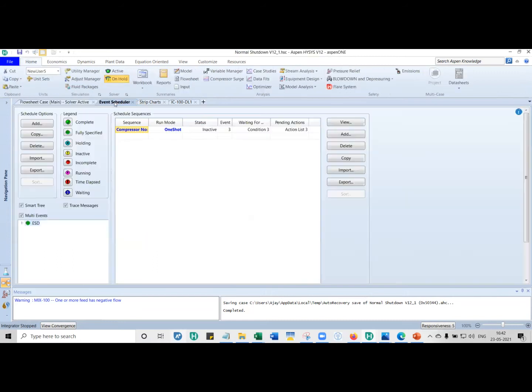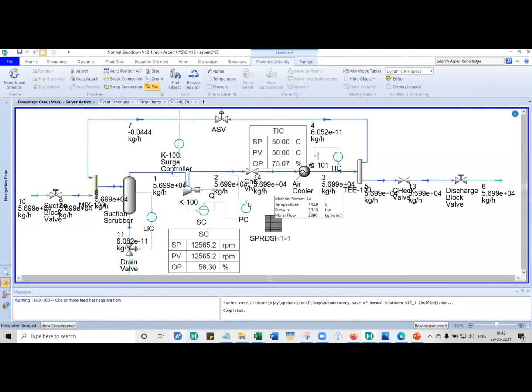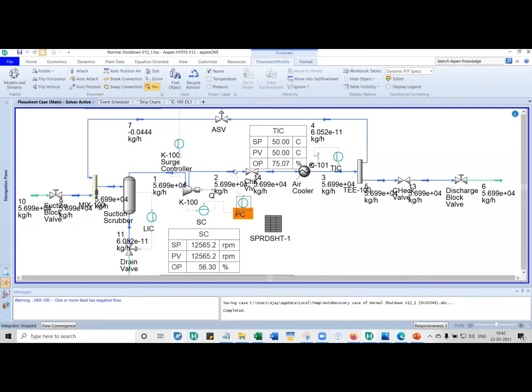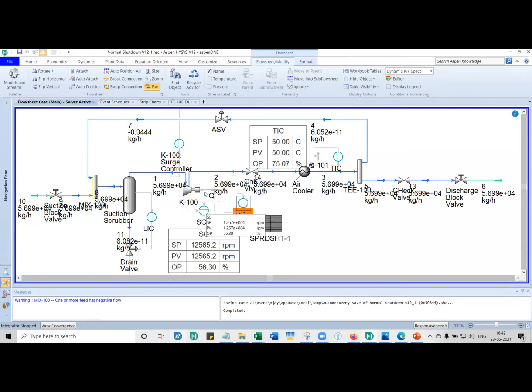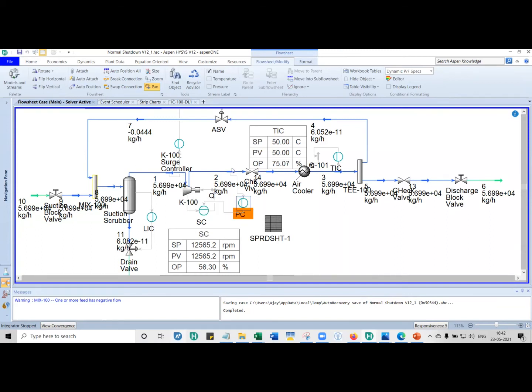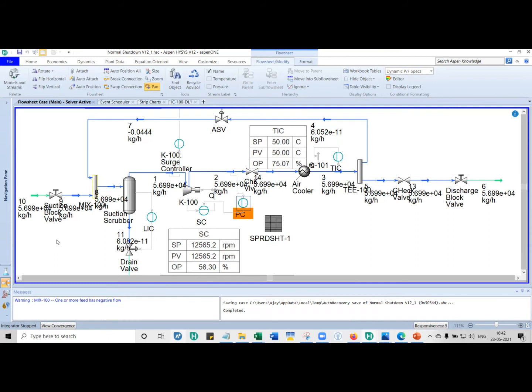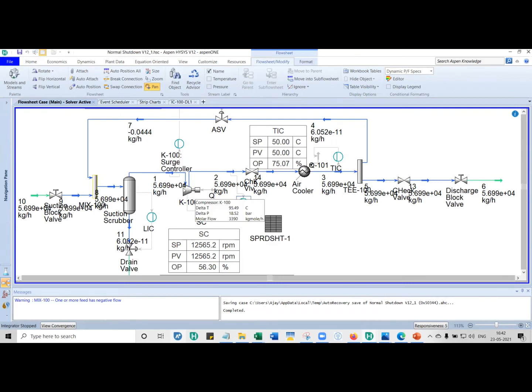Event scheduler, the purpose is to automate the whole thing. This is a case of normal shutdown. In this model, if you observe, you have a pressure controller which gives a set point to the speed controllers. If the pressure is too high here, you have to reduce the speed. The pressure is too low on the discharge, you increase the speed. When I'm doing a normal shutdown, if I trip the compressor during the shutdown, I want the compressor to be independent. I don't want it to be influenced by anything else.